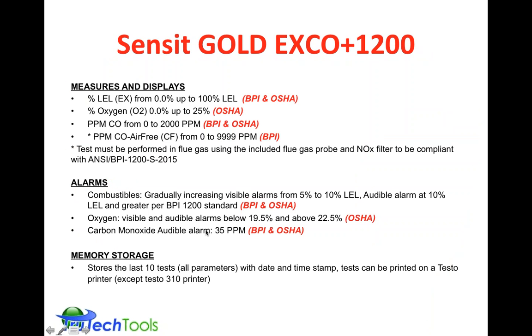So in its hybrid mode here, it covers the BPI standard for the LEL display and also the OSHA standard for oxygen, BPI and OSHA for CO, and the CO air-free spec for BPI. It has the alarms that BPI and OSHA require: the oxygen for OSHA, the carbon monoxide alarm for BPI and OSHA. And on top of that, it gives you stored test data with a time and date stamp, and the last 10 tests can be printed through its infrared port onto a testo printer.